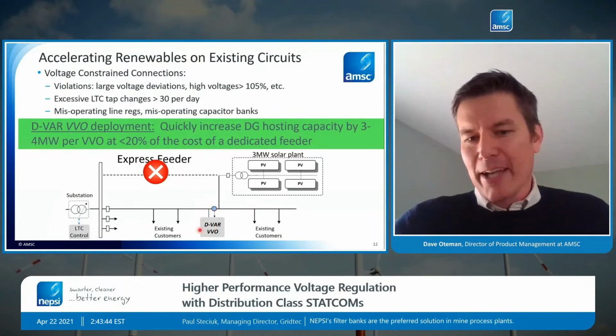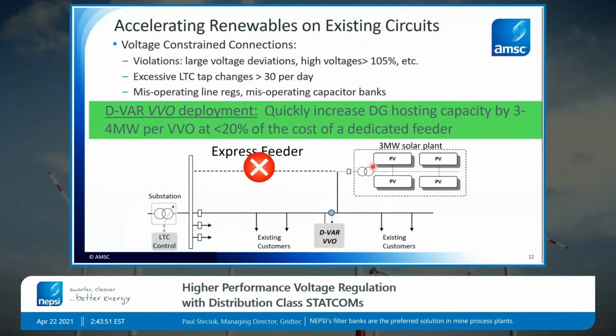What I'm showing here is on the utility system, where the utility would own the STATCOM. It's also possible to have STATCOMs at the solar plant. There are a lot of advantages to having the STATCOM located on the main feeder, including making sure all existing customers have excellent power quality and are protected against not just this solar plant, but potentially future solar plants coming onto that system. Whereas if you have the STATCOM behind the fence at the solar plant, those benefits of protecting existing customers and utility assets are harder to achieve.